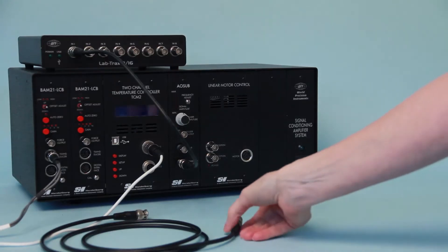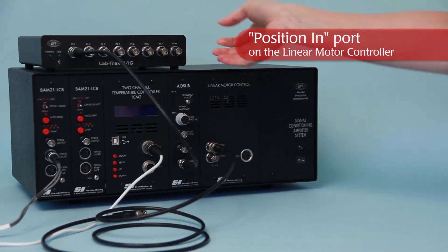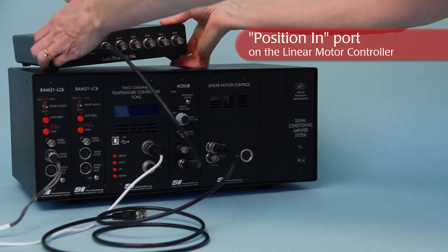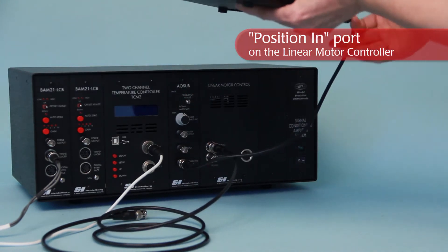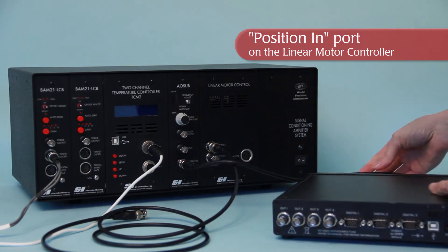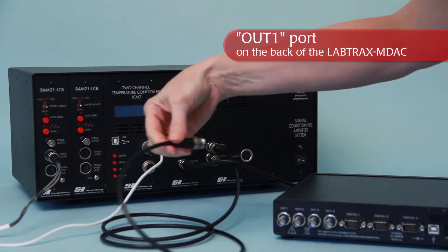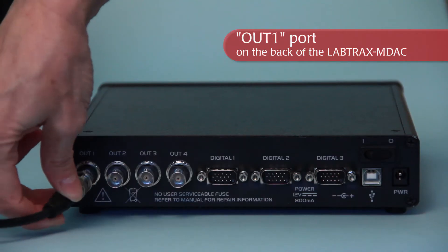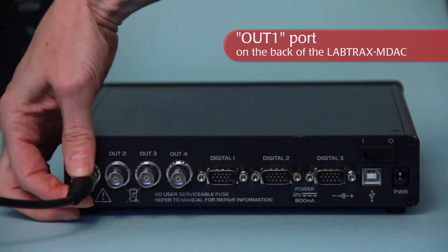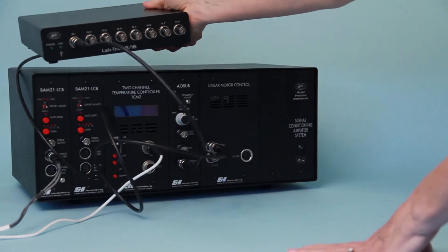If a motor is going to be used to stretch and relax muscles, it is controlled by an analog output of the data acquisition system. Connect a BNC cable to the socket on the front of the position control module labeled Position In. Connect the other end of this cable to the analog output on the data recording device designated for the position protocol, like the OUT1 connector on the back of the Labtrax MDAC.